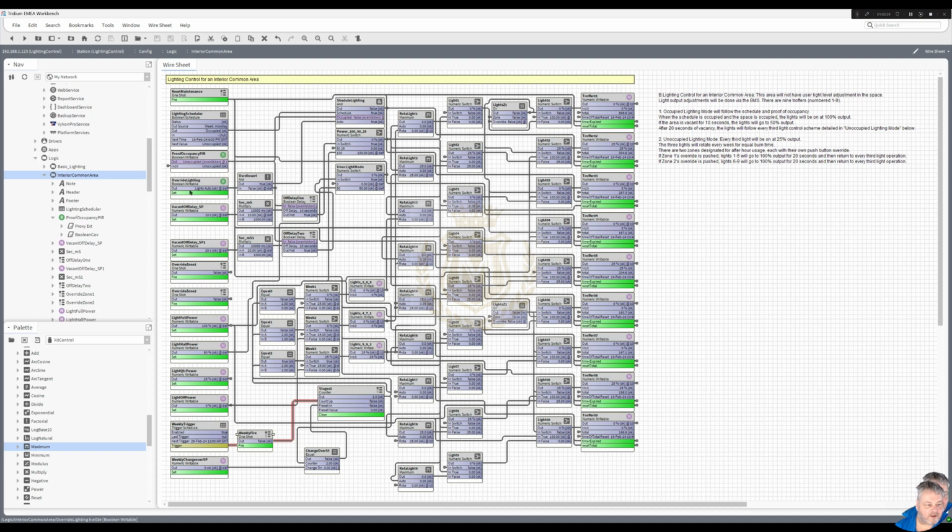The zones 1 and let's just see while we're in this position where they're off. Let's just do an override for zone 1. There we go. Actions. Fire. Zone 1's all 100%. Do an override for zone 2. Fire. Zone 2's all 100%. And then they will go off after 20 seconds, which is that adjustable one there. They've not gone off yet. Still waiting for these to go off. Yeah, they're all off. Back to your 25%.